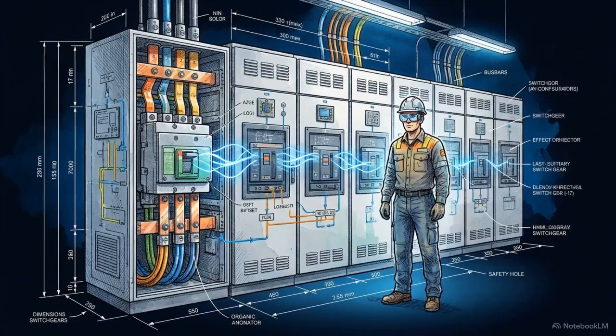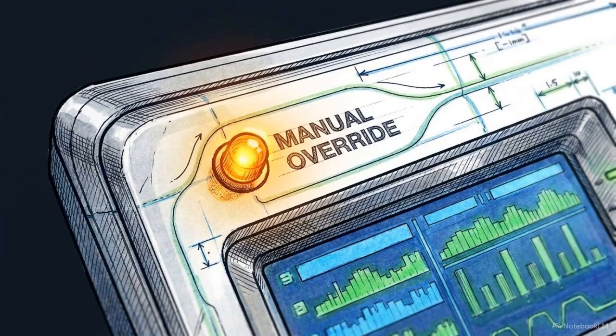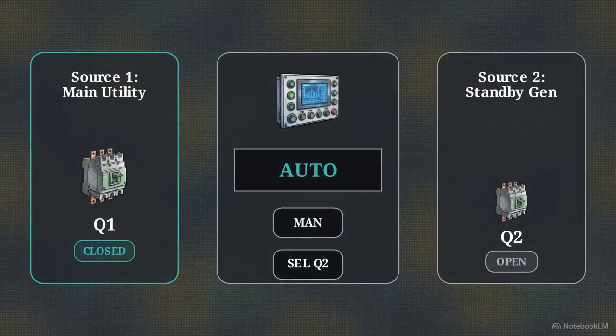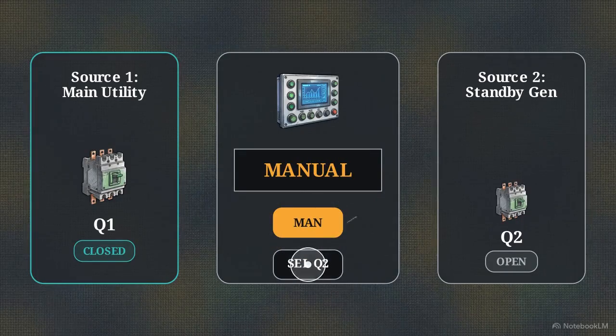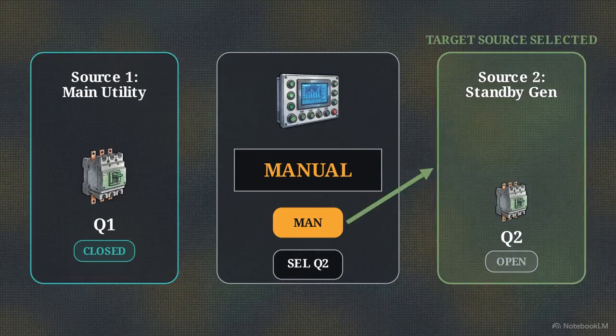We rely on manual mode for authorized testing, commissioning, or controlled maintenance. It suspends automatic source priority logic and is never used for unprompted day-to-day operation. Starting from a stable grid on source 1, you press and hold the manual key to take control of the logic board. Once in manual, you select Q2, the standby generator, as your specific target source.